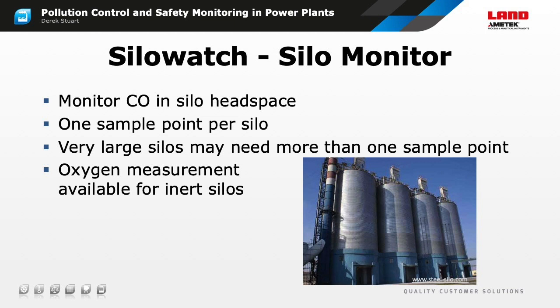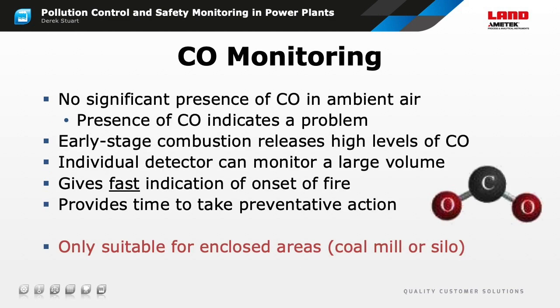Very large or highly asymmetric storage volumes may require additional sample points to ensure adequate coverage. Some silos employ a nitrogen blanket to reduce the risk of spontaneous combustion, so an oxygen concentration measurement is used to confirm that the gas injection rate is sufficient. The power of CO monitoring comes from the fact that CO concentration in ambient air is very low, even in an industrial environment, so the presence of CO gas is a clear indication that something is going wrong.